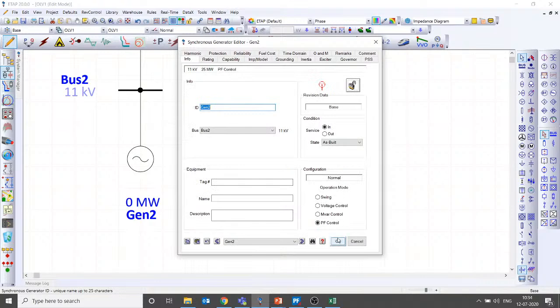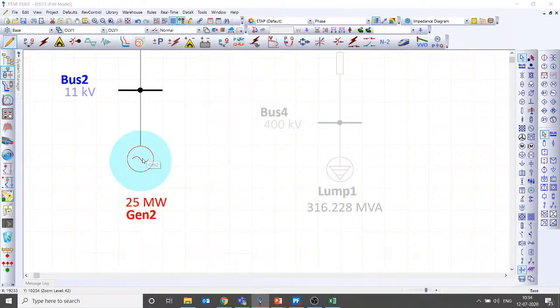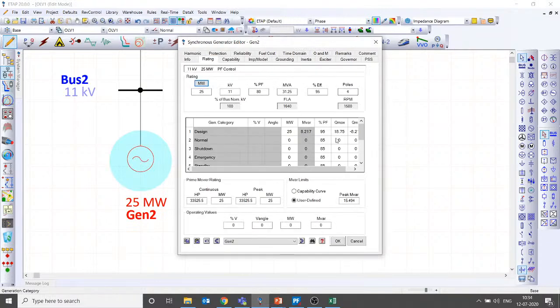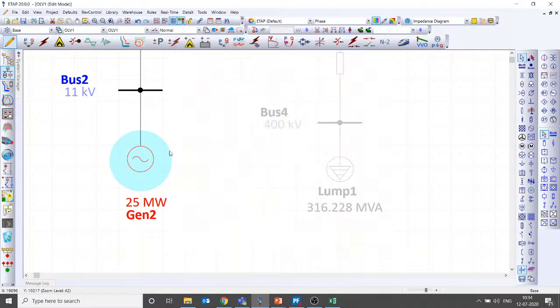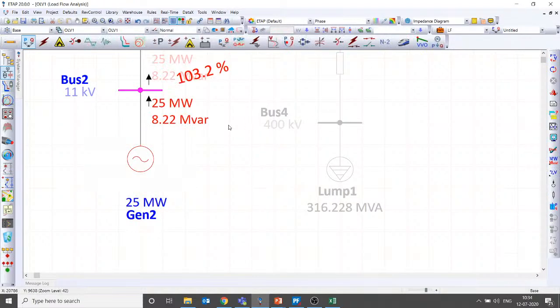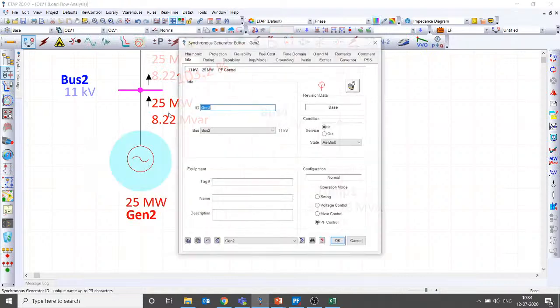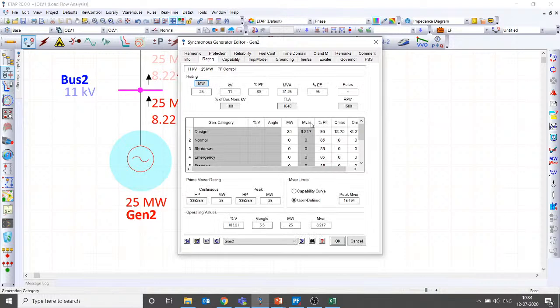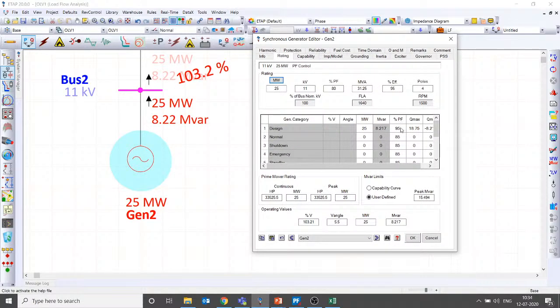Yes. So now let us operate this generator in power factor control mode itself. If I put the generator in power factor control mode and set the power factor as 0.95, then it generates 8.217 Mvar. If I change the power factor, the reactive power changes. The beauty is, I am retaining my power factor at 0.95 and changing the real power generation, from 25 megawatt to 20 megawatt. So you can see the generator capacity is 25 megawatt, but that doesn't mean it has to generate 25 megawatt. It can generate 20 megawatt also. When it is generating only 20 megawatt, the reactive power generation, which was something else previously, has now come down.